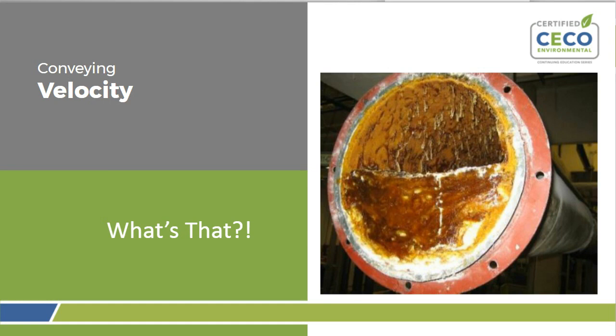Velocity, like Vern was saying, is very important. If you don't have the correct velocity, what you're going to end up with is what you see in this photograph, with the duct being half full of contaminant. That's problematic in that you've reduced your area, changing your velocity profile, with higher static, and you're not going to get the overall system volumetric flow rate that you need. And if it fills up too much with a material that's heavy, the duct could collapse and harm people in the plant and contaminate the plant if the material is bad stuff.